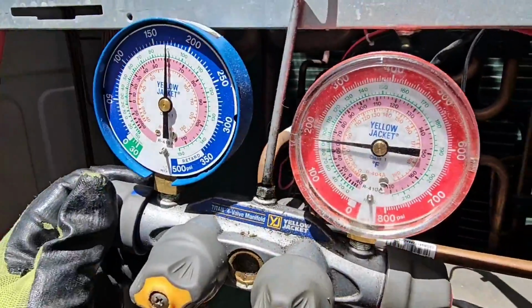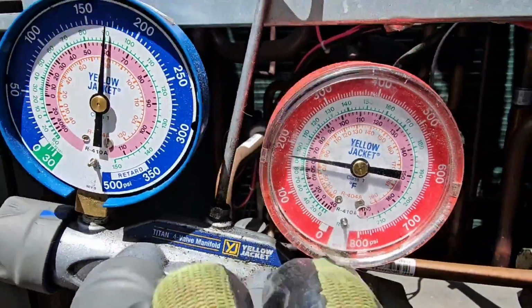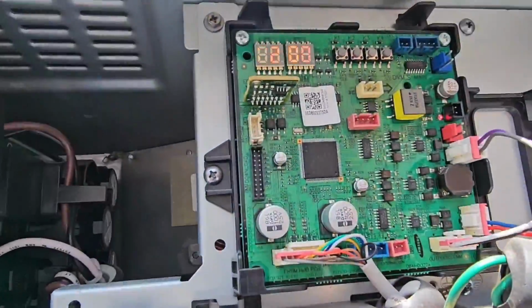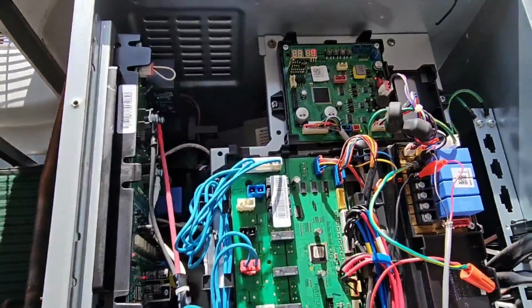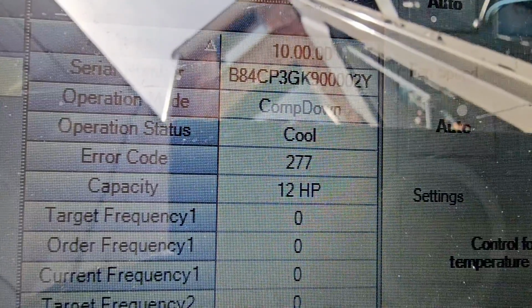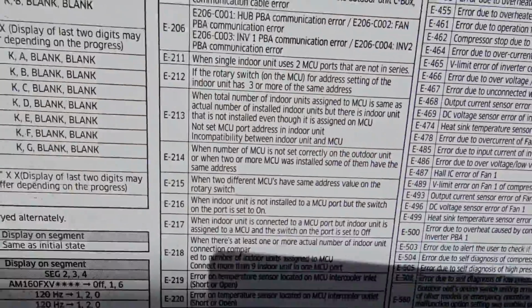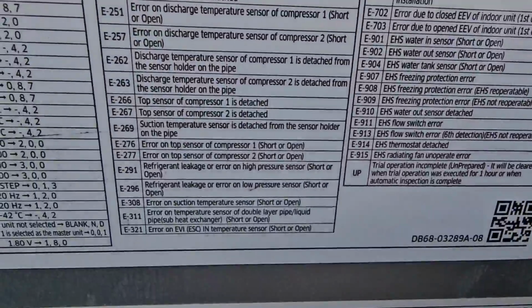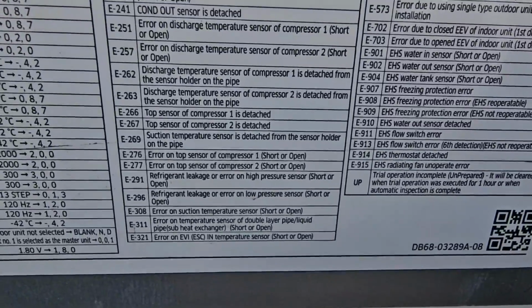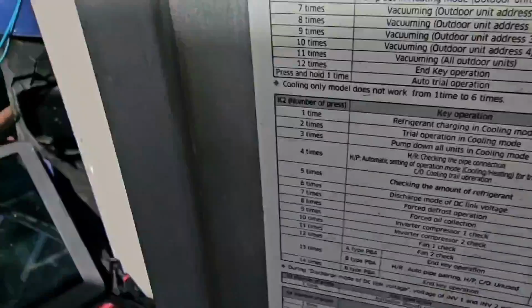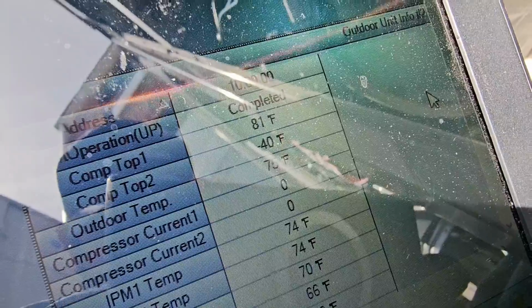So we should have pressure now. We got pressure, yeah. Okay, so we shouldn't have that error code now. Oh wait, we do have an error code. Error code 277. It looks like we got an error code E277. And if we look right here, that means error on top sensor of compressor 2, short or open. So if we go over here and look at our outdoor unit data, we can see compressor 1 top's 81 degrees. That's right. Compressor 2 top, negative 40 degrees.